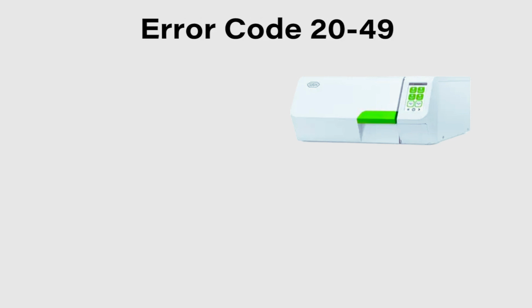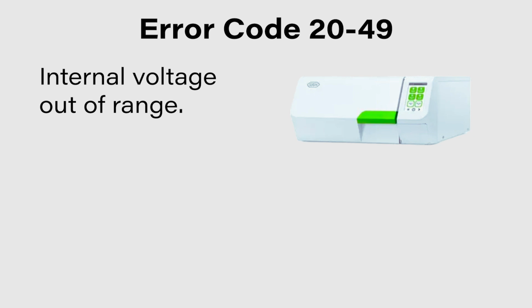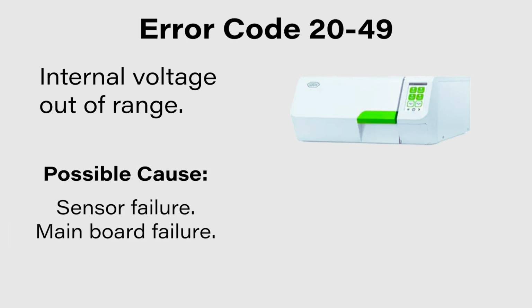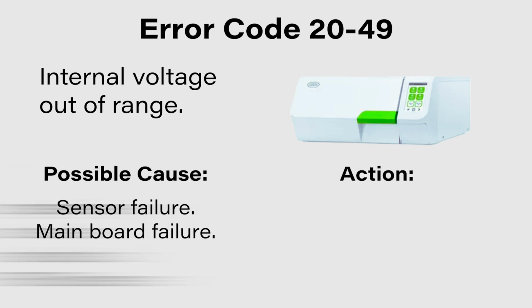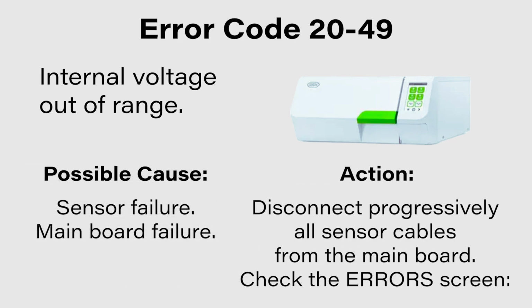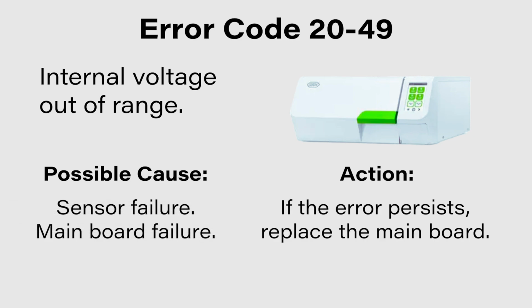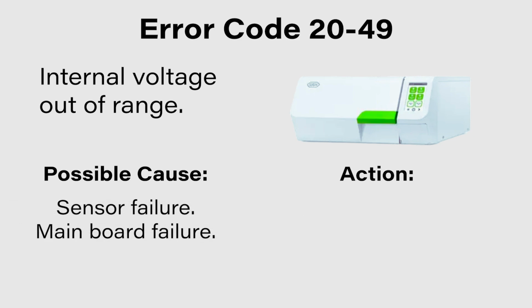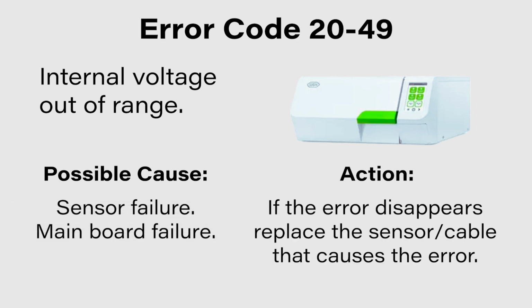If your W&H Lexa Mini Autoclave is displaying an error code ranging from 20 to 49, that means there was an internal voltage that was out of range. The possible causes are a sensor failure or a main board failure. For this, disconnect progressively all sensor cables from the main board. Check the errors screen. If the error persists, replace the main board. If the error disappears, replace the sensor or cable that causes the error.